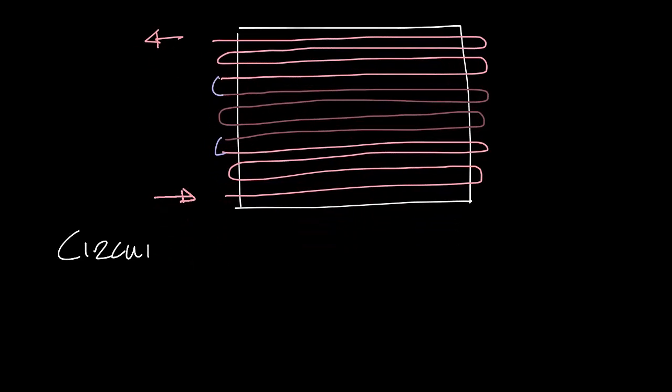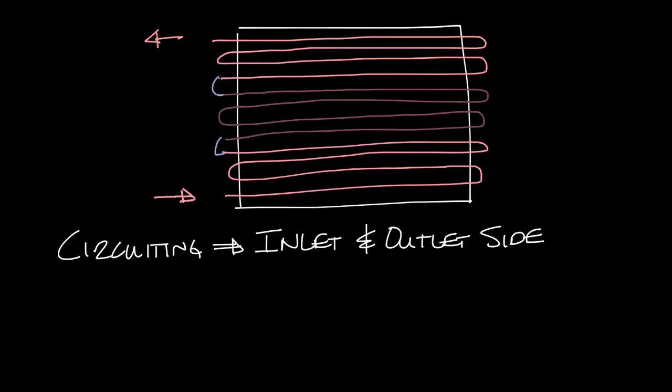So this may be possible but there's a couple things that circuiting in a water coil does. First you want to get the inlet and the outlet of the water coil on the correct side. Usually this means on the same side, so all your piping connections come to the same area.